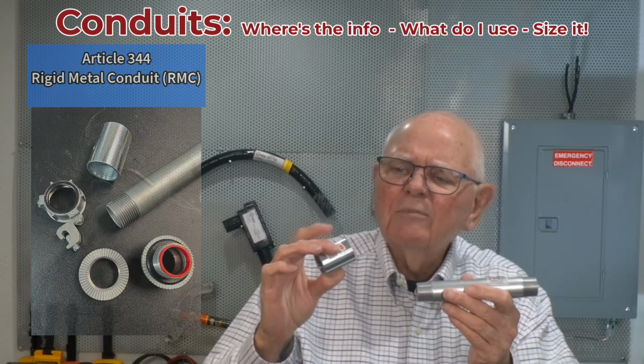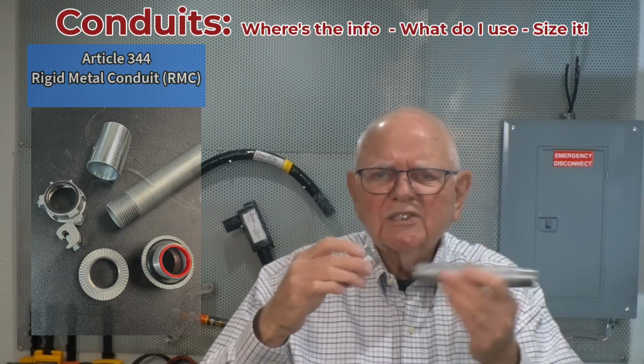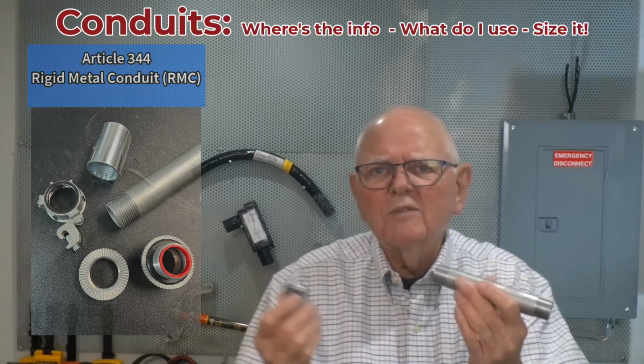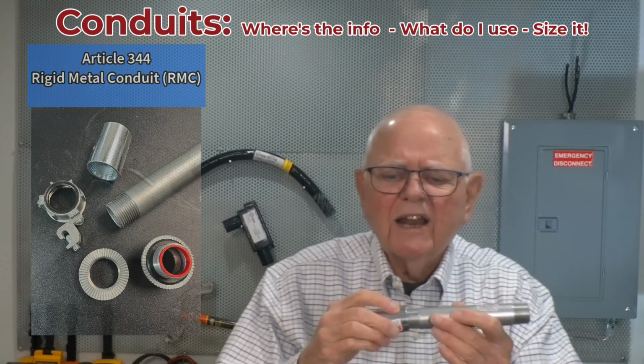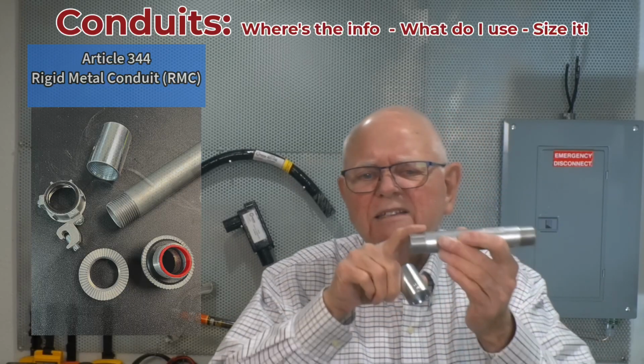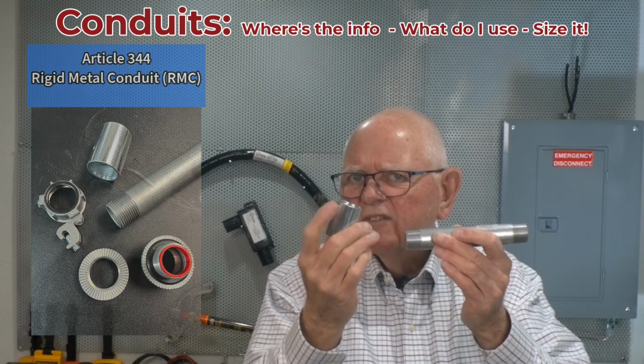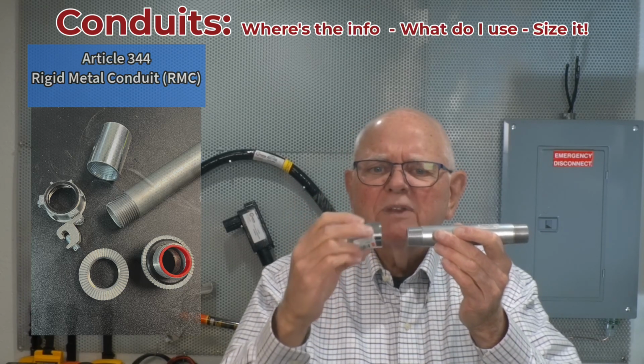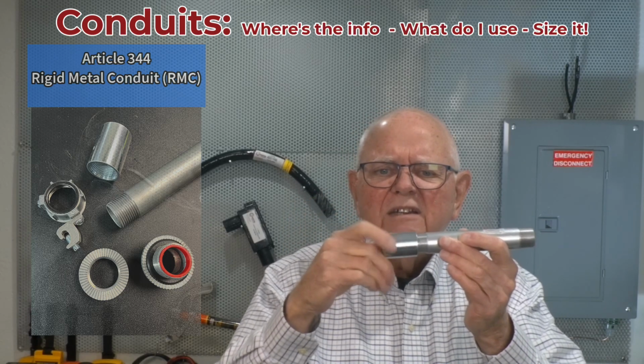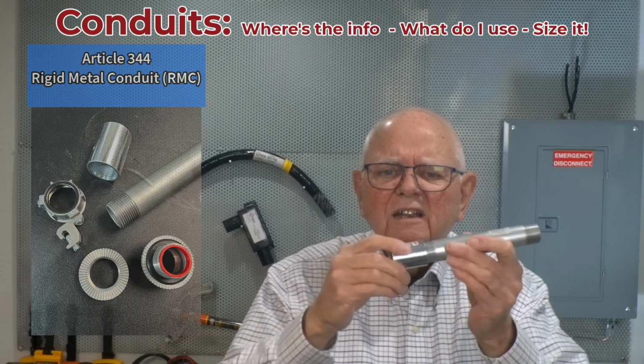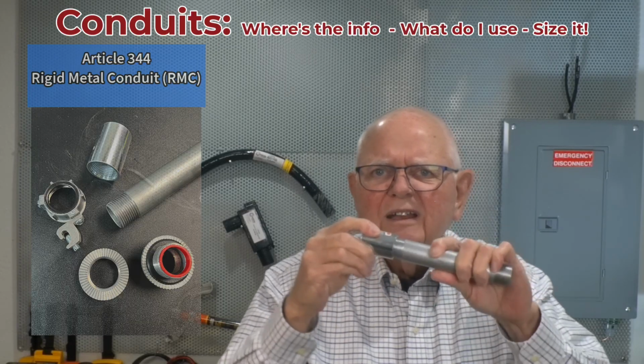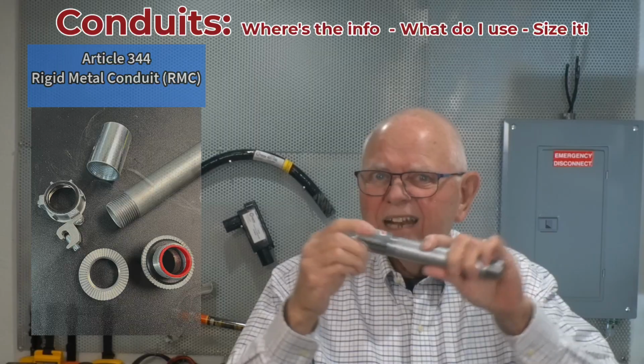In this case, my coupling has straight threads. We're going to see in Article 344, one of the important things with rigid is that I make it up wrench tight. If I've got tapered threads here and straight threads in this coupling, and I put this coupling on and just take a few threads, it's pretty loose. Well, that's not good.